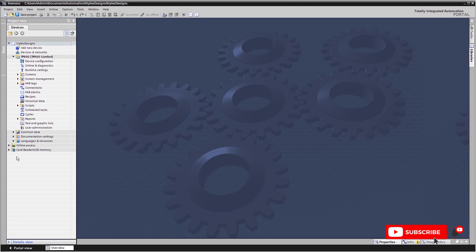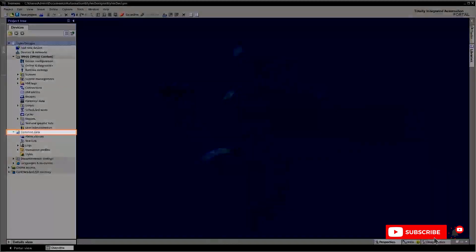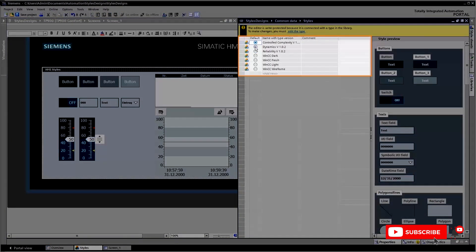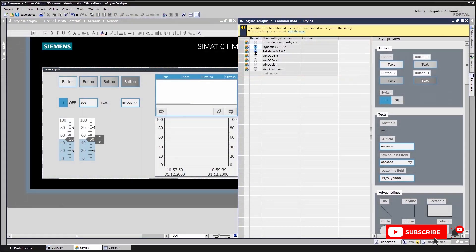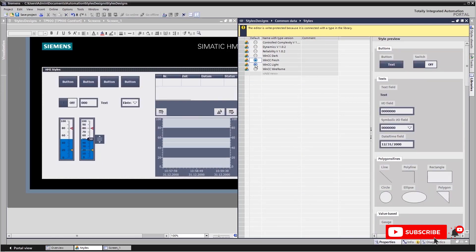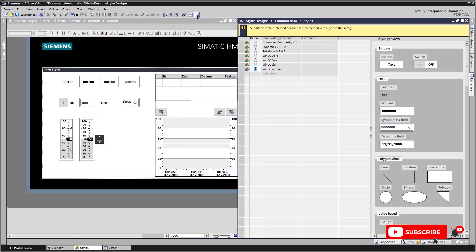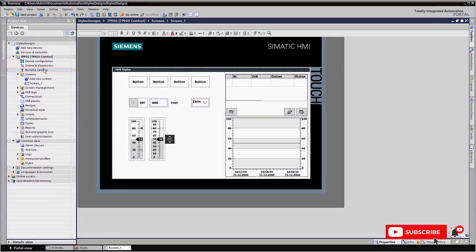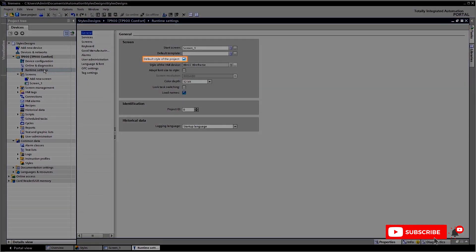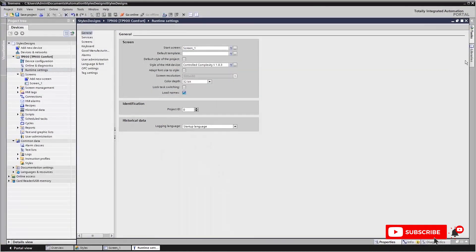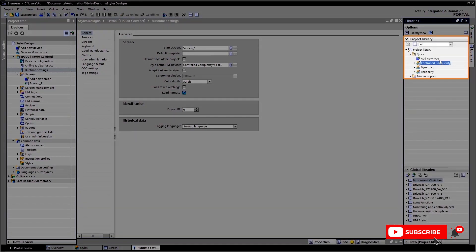In the TIA Portal, you administer your styles via the common data styles folder in the project tree. Here you will find all the styles available in the project, including those already included in the scope of delivery. You can modify them as needed or create individual styles. In the runtime settings of the operating device, you can specify whether the HMI device should observe the project-wide style or the device-specific style.